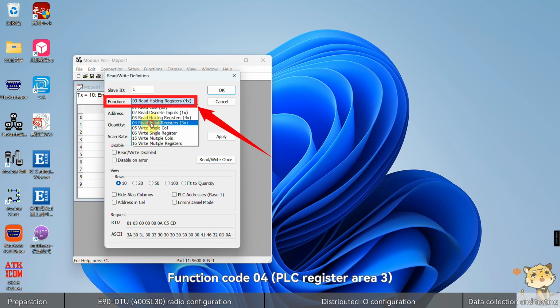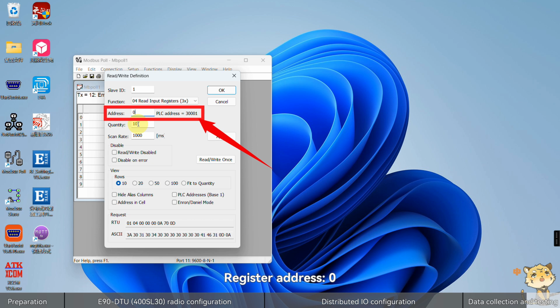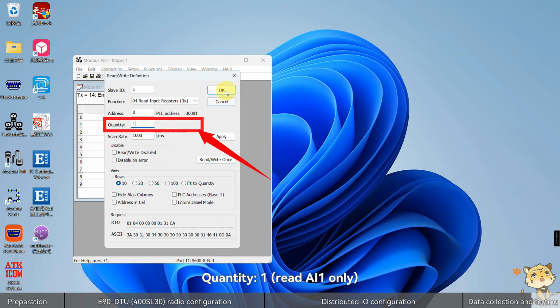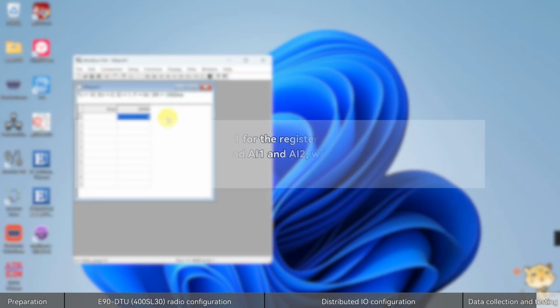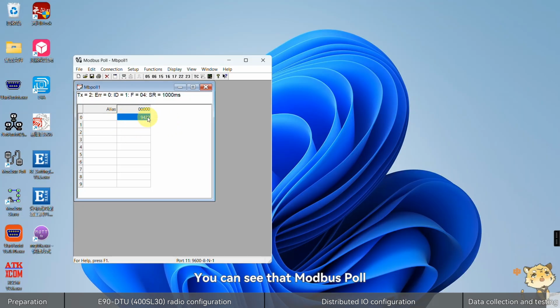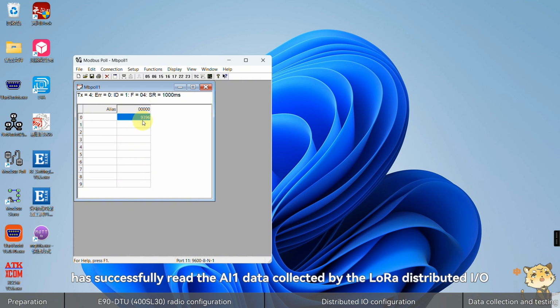Function code 04, PLC register area 3. Register address 0. Quantity 1, read AI1 only. Click OK. You can see that Modbus Poll has successfully read the AI1 data collected by the LoRa distributed I/O.